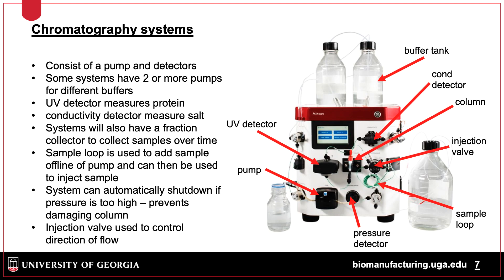There are different chromatography systems available and, depending on the process, will be used with smaller or larger columns. The most basic system consists of a pump and detectors. Some systems can have multiple pumps, which are used with two or more different buffers. The detectors are typically a UV detector to measure protein, as well as a conductivity and pH detector.